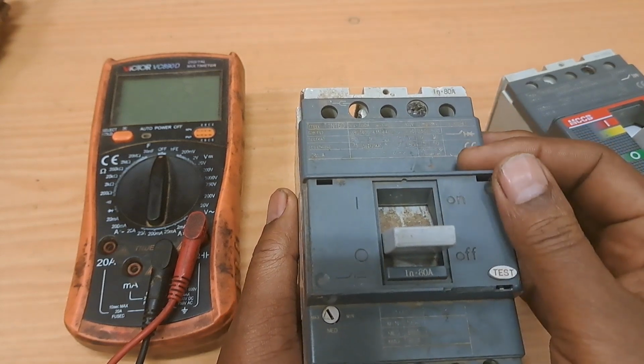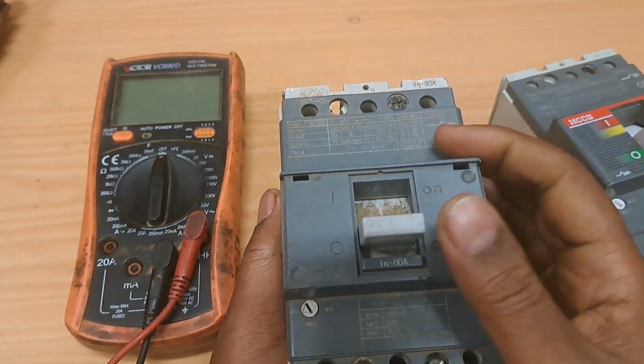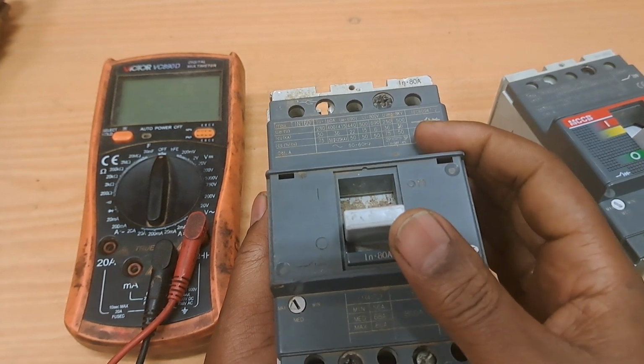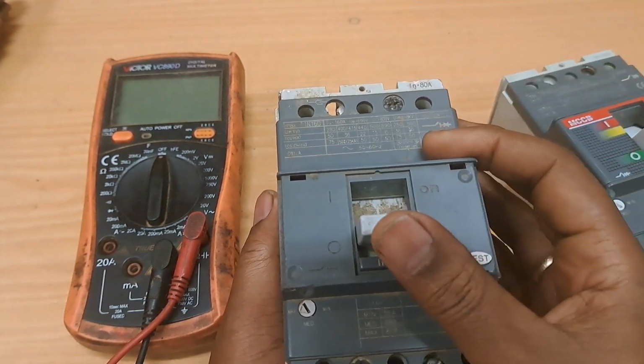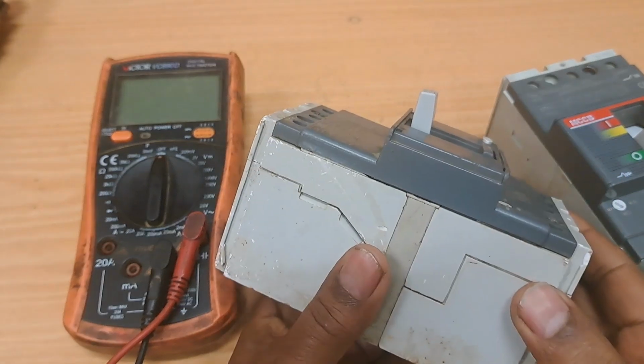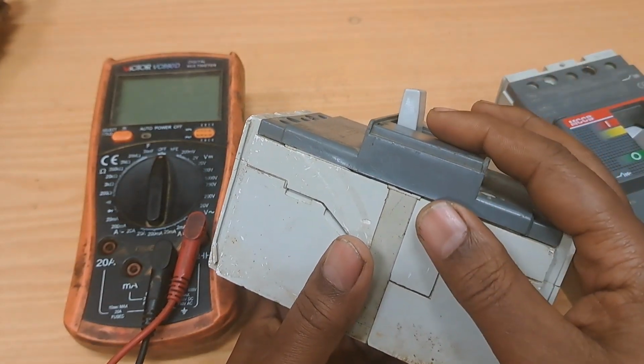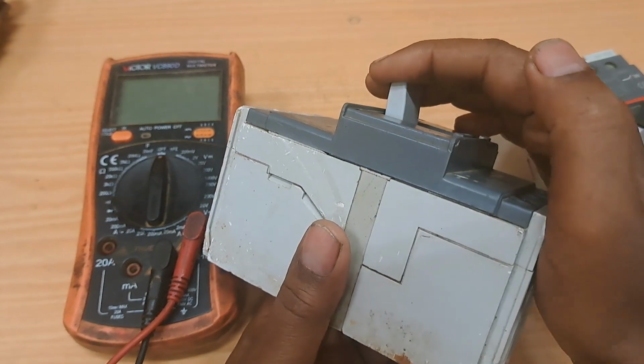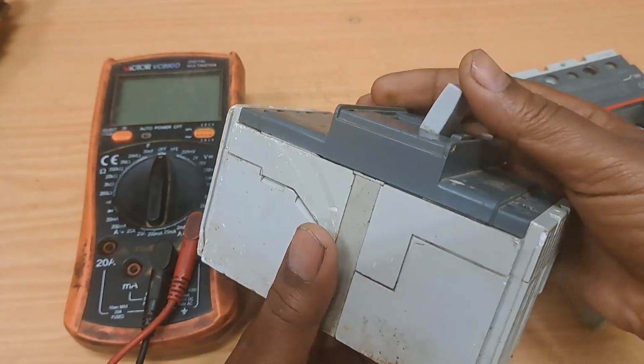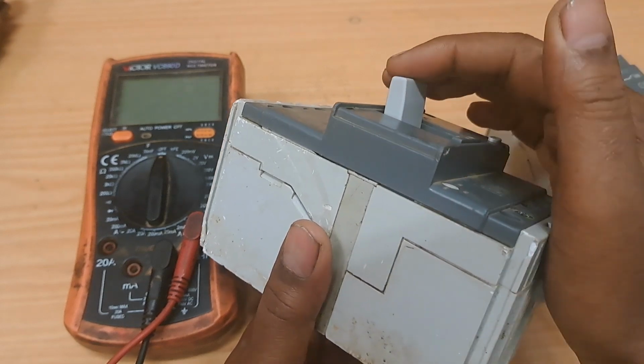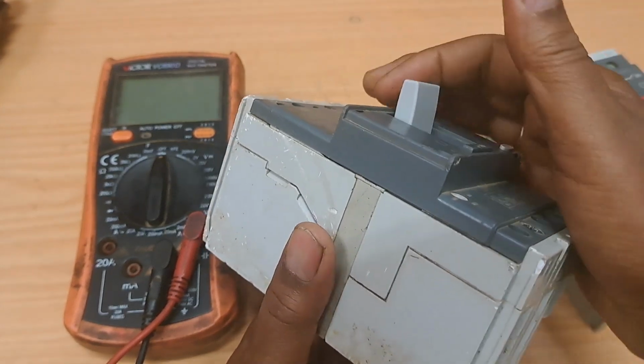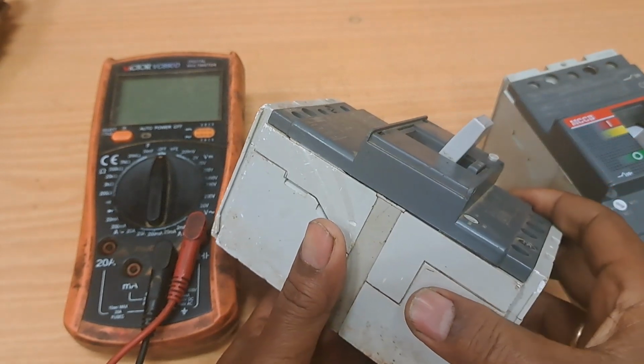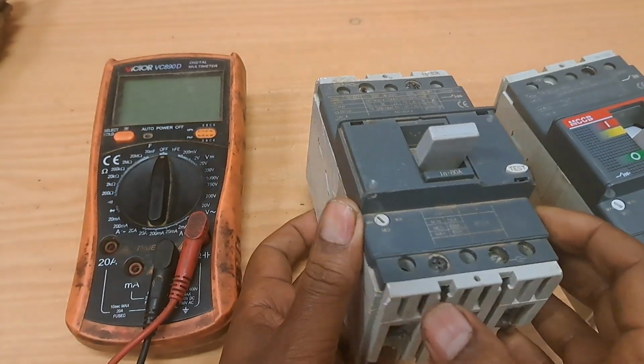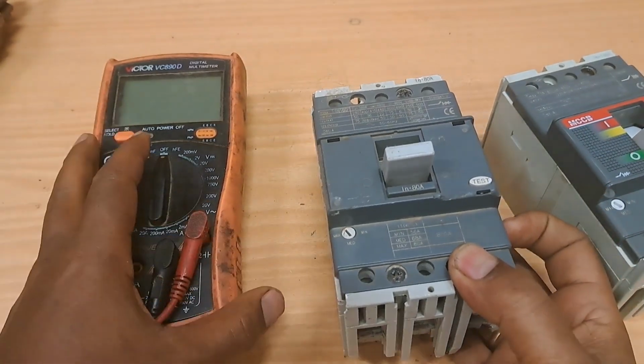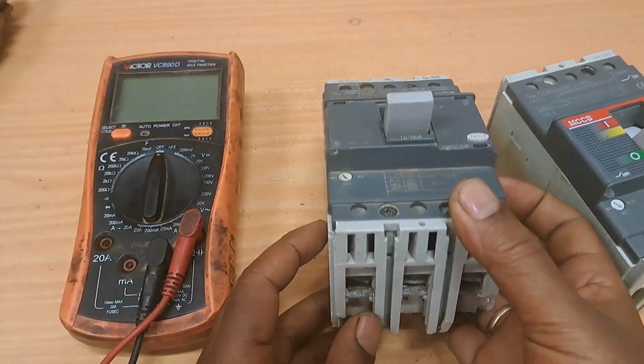When you turn it on, you should hear a very strong latching sound as a spring snaps into contact. Listen, this is very nice. Now it is closing with a very nice spring load. It should turn off and on easily. This is one method of inspecting. If it is not moving freely like so, it is defective. Then go ahead and use a multimeter to see if it is electrically good or not.